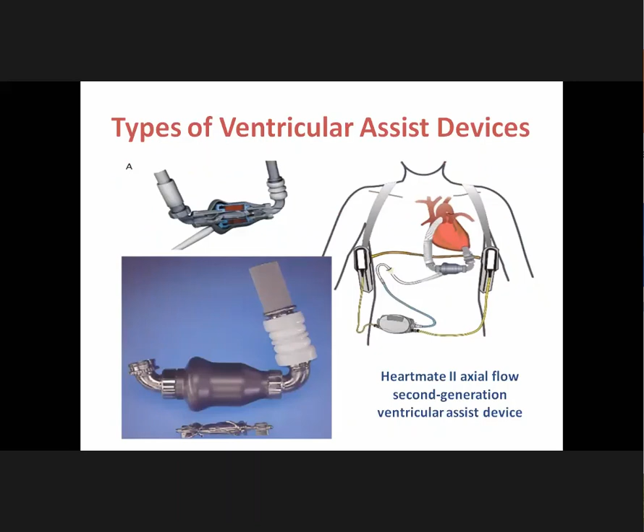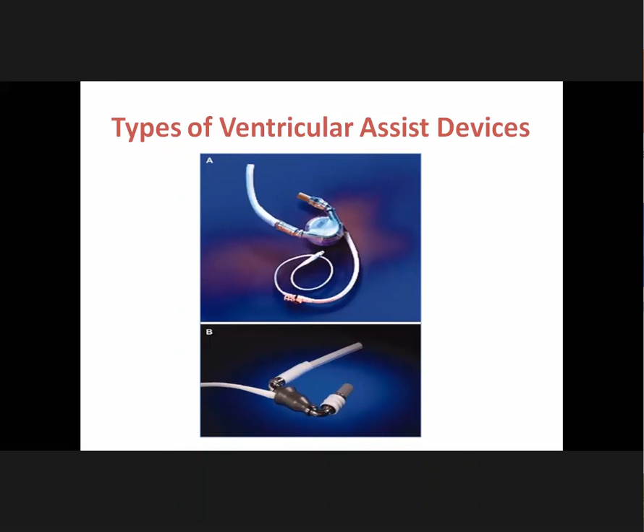This is the HeartMate 2, which is an axial flow, second generation ventricular assist device. See, when compared to the first generation ventricular assist device, the size of the HeartMate 2 has come down drastically, and the technology also has changed, where the first generation is a pneumatically driven system when compared to the second generation device, which is more of an axial flow system which runs with a motor with rotor blade.